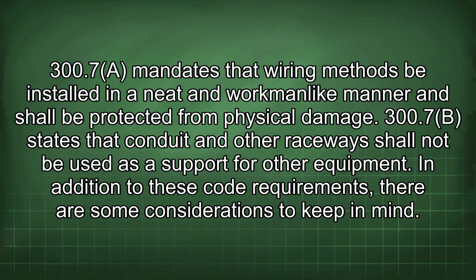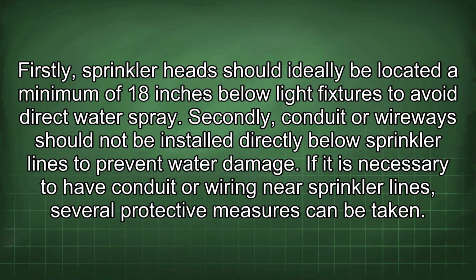In addition to these code requirements, there are some considerations to keep in mind. Firstly, sprinkler heads should ideally be located a minimum of 18 inches below light fixtures to avoid direct water spray. Secondly, conduit or wireways should not be installed directly below sprinkler lines to prevent water damage.